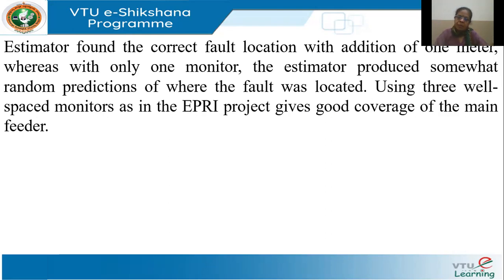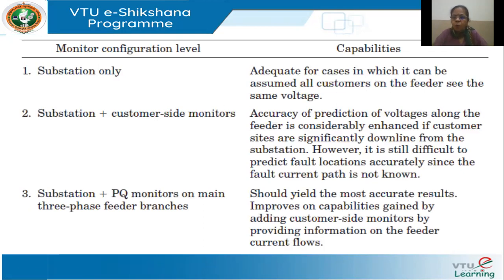What EPRI has said is that if we have three monitors along each feeder, one at the substation and two at the feeder levels, it gives excellent coverage, and most of the faults can be located accurately, and the estimate of the power quality, that is, the voltage deviations, is accurate. This is what their finding shows. So we'll just see here what happens with different monitoring. If I place a monitor only at the substation, this is okay if all the customers on the feeder see the same voltage.